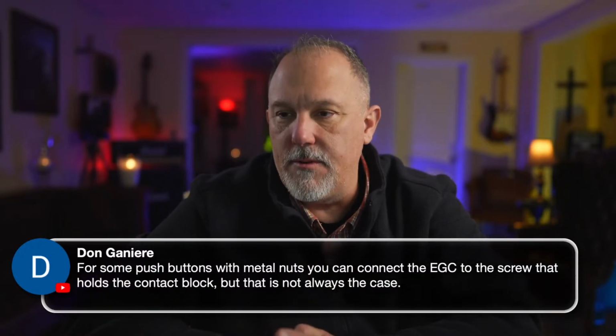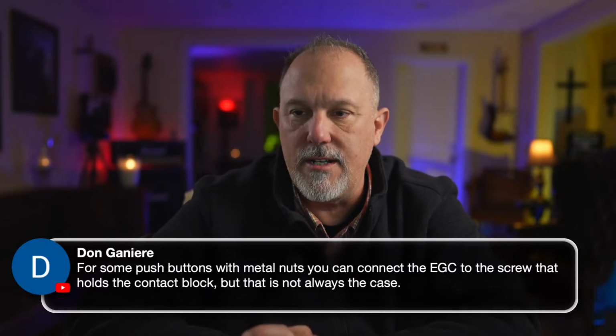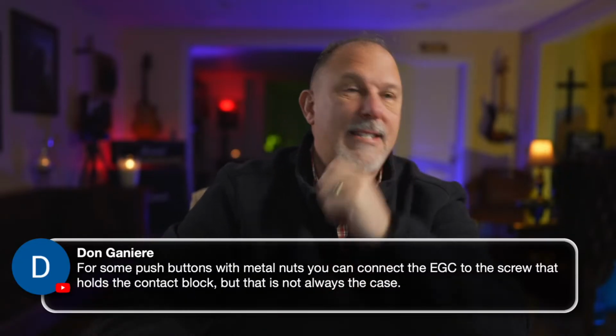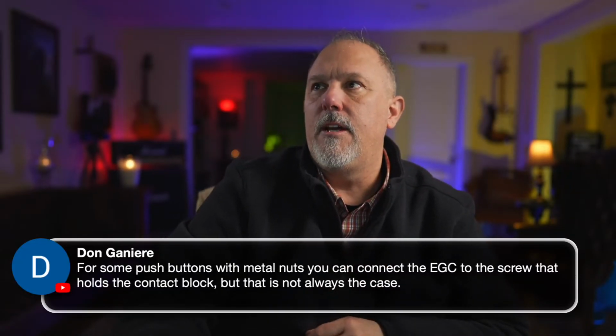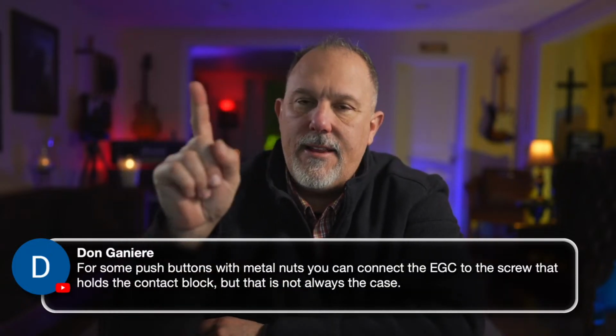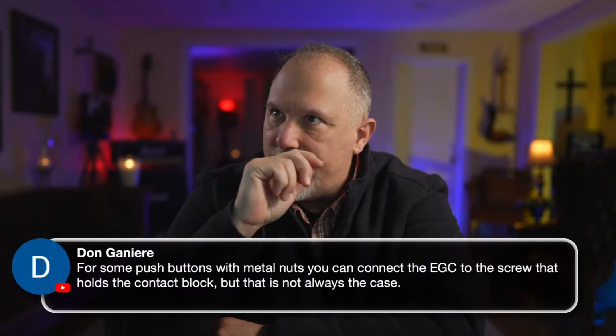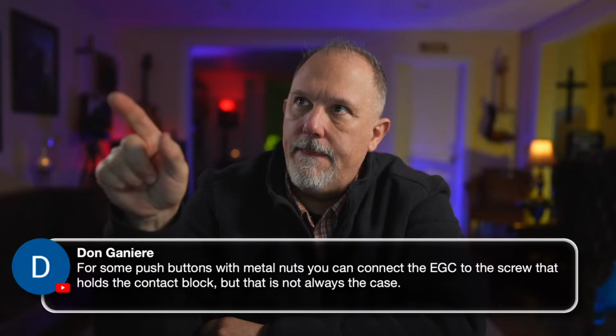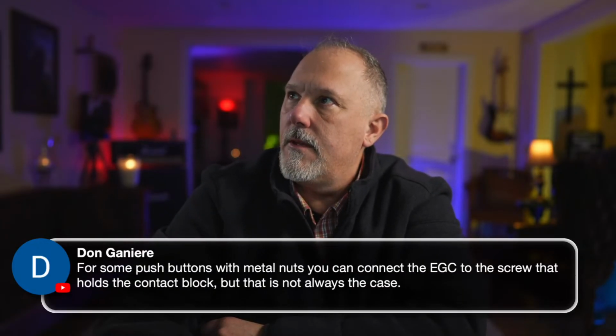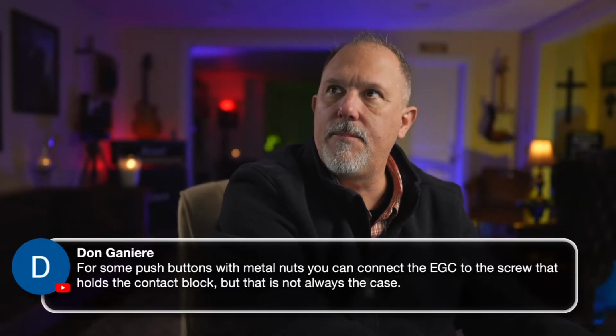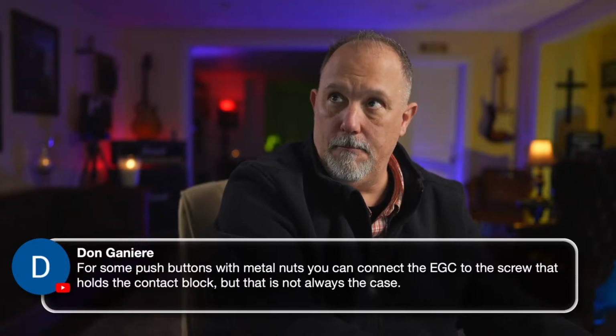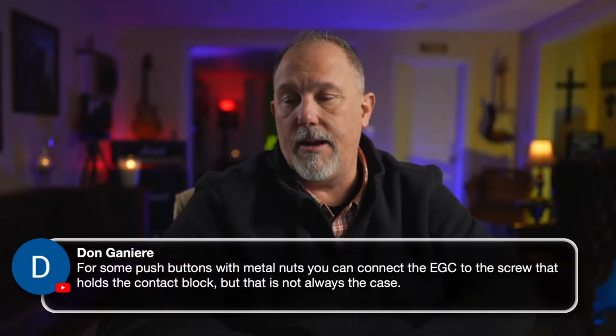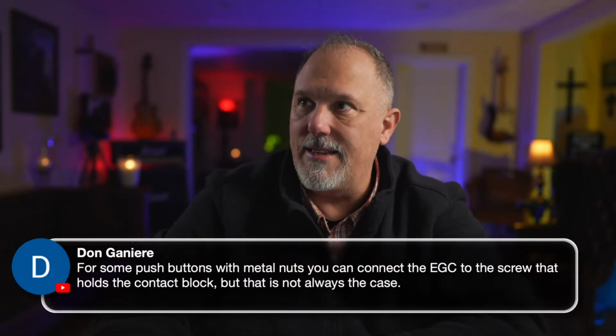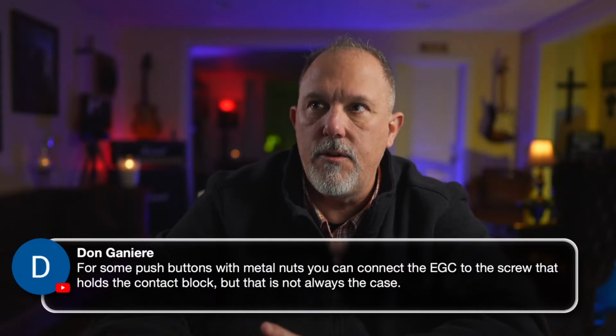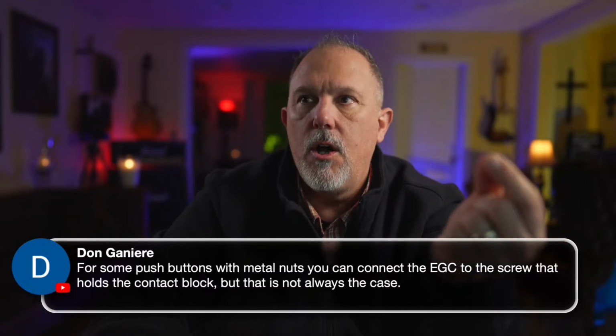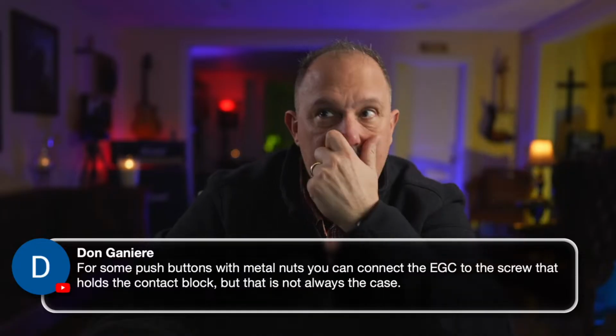For some push buttons with metal nuts, you can connect the EGC to the screw that holds the contact block, but that is not always the case. So here's my thought process. What was not said in this question, it says start and stop switches and relays. Start and stop switches for motor control. Are we saying that there is no equipment grounding conductor? There's no green terminal on the back of those switches? Is that what we're saying, Don?